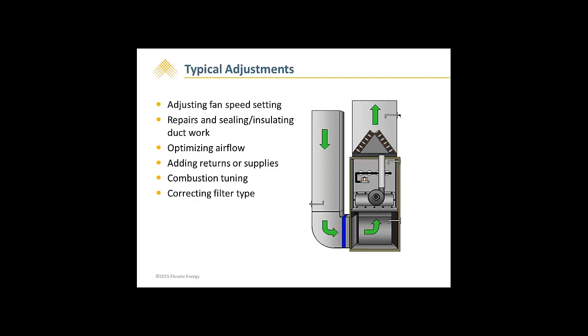If the pressure drop over the A coil is high, this could be a sign that the A coil is dirty or it's not sized properly for the equipment. If you have too much total external static pressure, this could be a sign of a few different problems. Other tests will be needed to confirm the issue. These results could tell you if you needed to address the fan speed setting or if you needed to add some more supply or return ducts. Some of these tests are relatively inexpensive, such as replacing the filter, tuning the combustion, or balancing the system, while other tests are more costly, like adding returns, supplies, or a full system replacement.